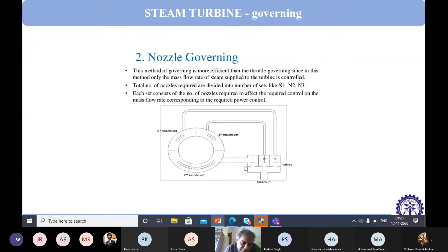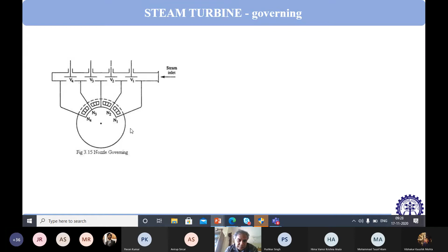There are different arrangements. This is another arrangement where we are showing how different sets of nozzles can be closed. So 4 sets have been shown. Now, bypass governing. Bypass governing is not as effective as the other governing I have discussed. It is some sort of emergency arrangement for when the turbine is occasionally overloaded for a short duration. During such operation, bypass valves are opened. So this is a bypass valve.